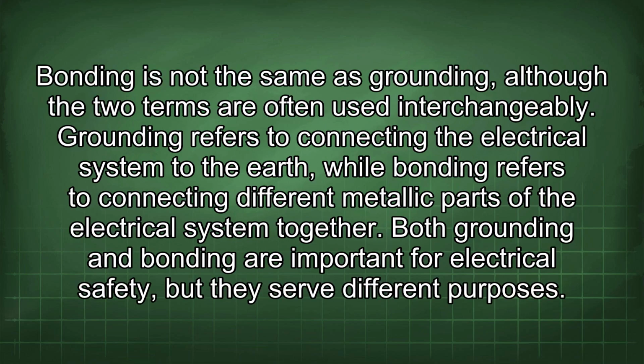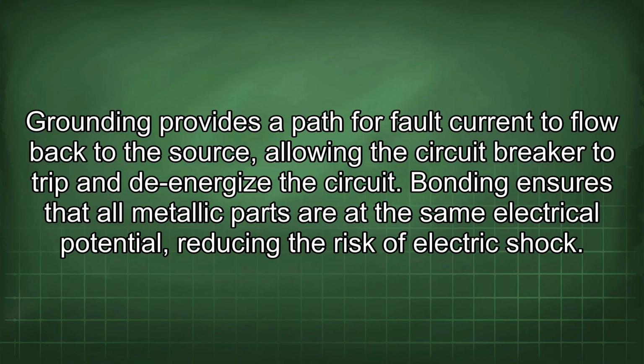Bonding is not the same as grounding, although the two terms are often used interchangeably. Grounding refers to connecting the electrical system to the earth, while bonding refers to connecting different metallic parts of the electrical system together. Both grounding and bonding are important for electrical safety, but they serve different purposes. Grounding provides a path for fault current to flow back to the source, allowing the circuit breaker to trip and de-energize the circuit. Bonding ensures that all metallic parts are at the same electrical potential, reducing the risk of electric shock.